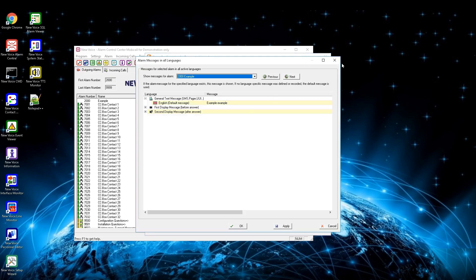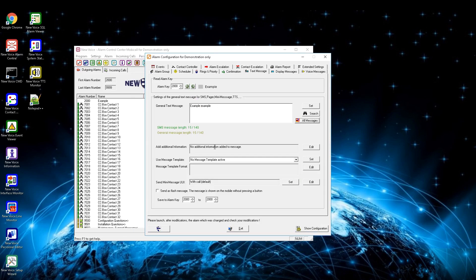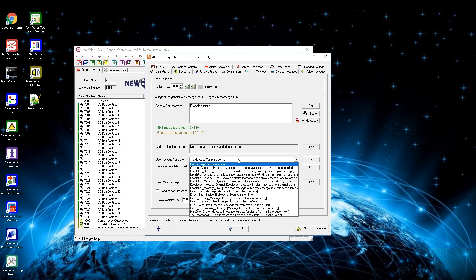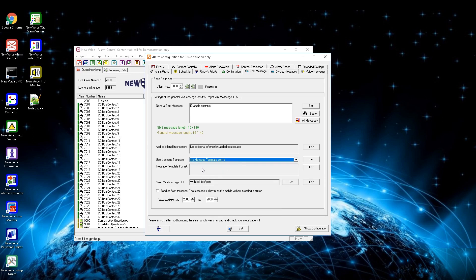With the setting add additional information, you can set which information should be sent with the message — possible options are the caller number who launched the alarm, a call-back number to confirm the alarm for an SMS receiver, or the caller name as provided by the PBX. With the message template drop-down menu, dynamic and static messages can be used together; MobiCall uses dynamic messages for the alarm and falls back to static if not existing, only if you want to combine a part dynamic and a part static message. With send mini message you can define if the mini message shall be sent with the call, after the call, or after a positive confirmation. The last checkbox sends an SMS as a flash message, shown on the display instantly without pressing read.